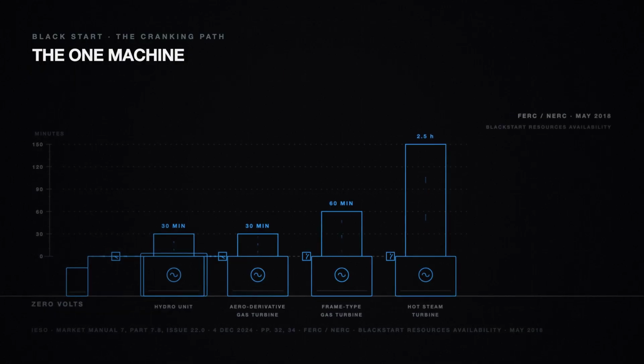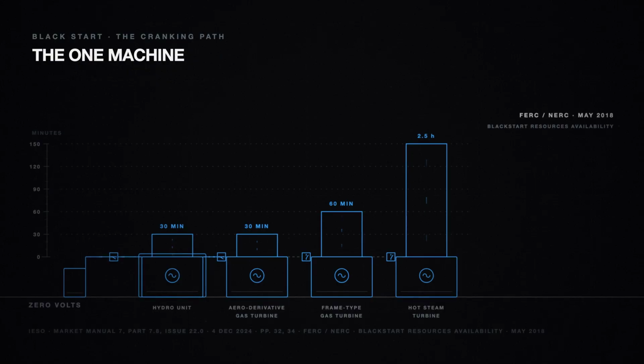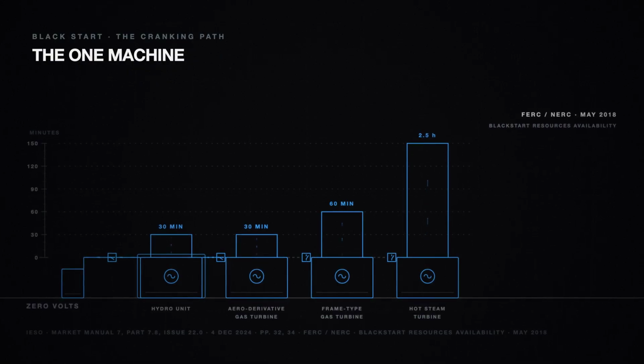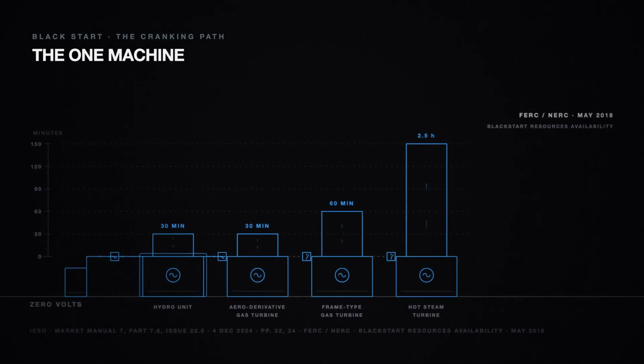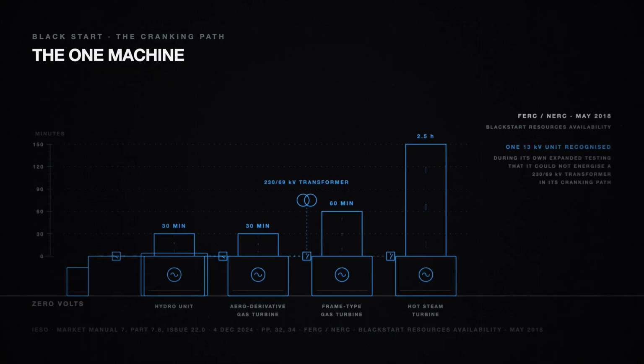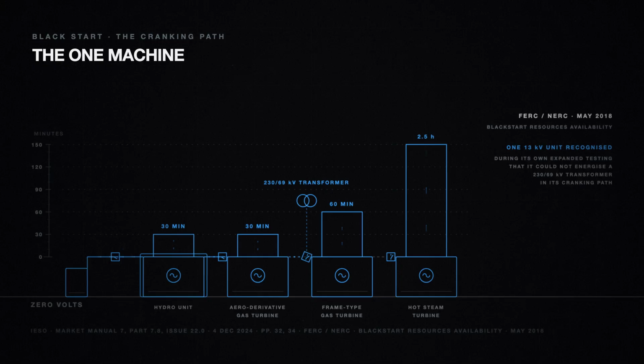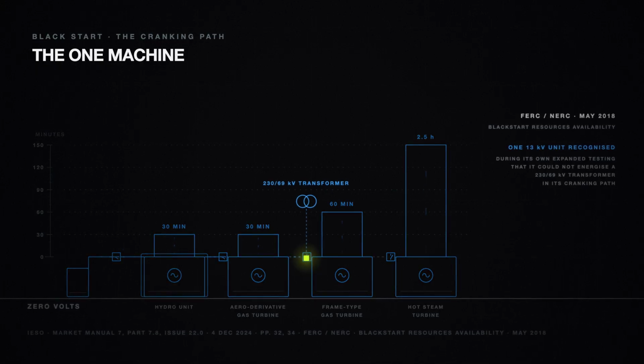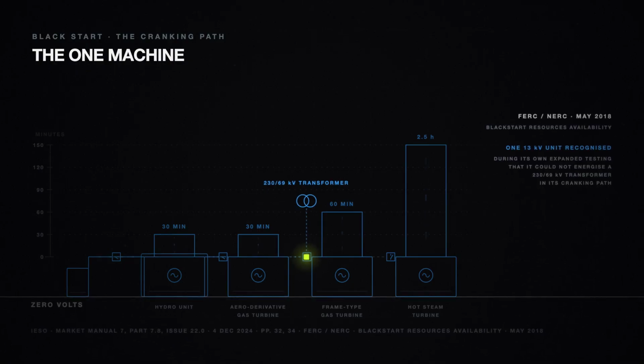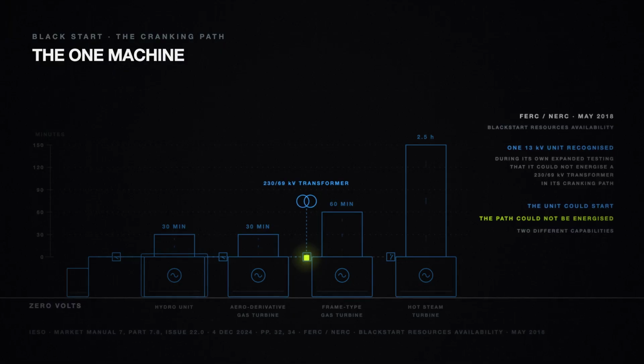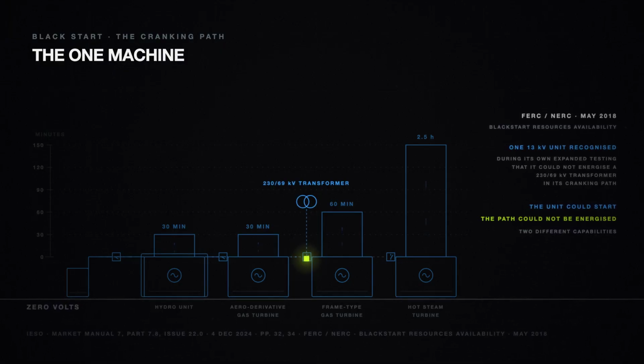Here is something somebody did measure. In 2018, the federal regulator and the North American Reliability Organization reviewed black start availability. One 13 kilovolt unit, they wrote, recognized during its own expanded testing that it could not energize a 230 to 69 kilovolt transformer in its cranking path. The unit could start. The path could not be energized. Two different capabilities, and only the first is what the phrase usually means.